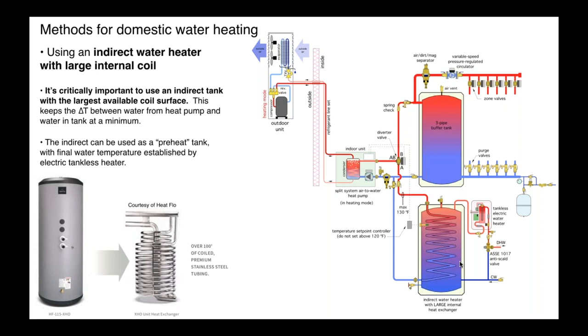So if you connect a heat pump to a very small coil in an indirect, the heat pump's going to short cycle. The water temperature is going to climb very quickly because the coil can't dissipate the heat into the domestic water as fast as the heat pump is producing the heat. So you've got that imbalance and the heat pump's going to just short cycle. It's going to shut off. And you're never going to be able to have good steady state operation. So if you go to this approach, get a tank that has the largest internal coils possible. I showed an example of one tank over there. There are some tanks on the market now that have dual coils. Probably connect them both in series so that you're taking advantage of the higher surface area of that internal coil.